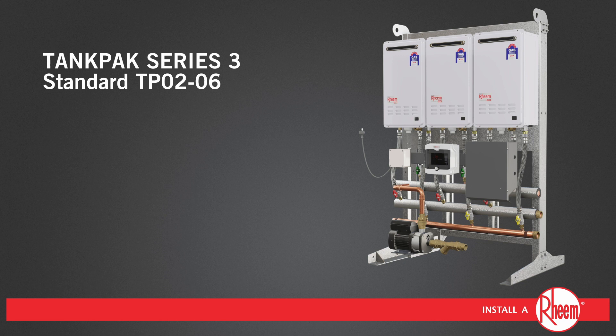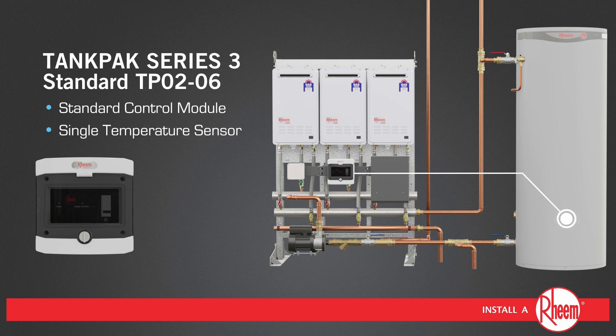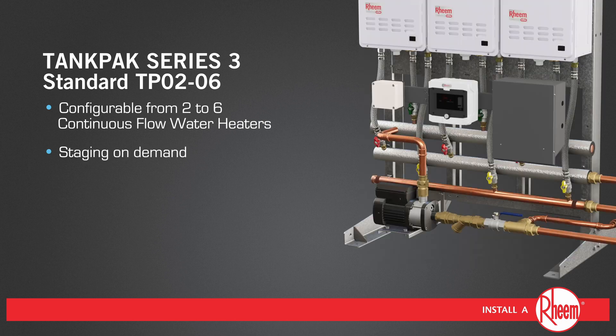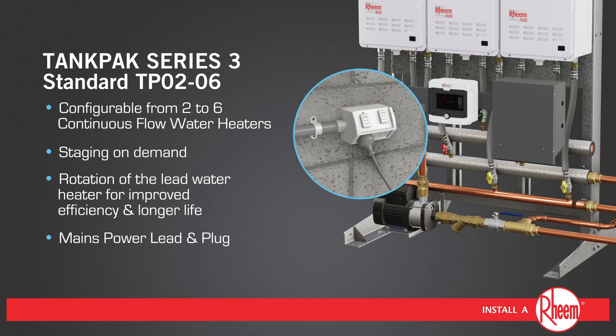TankPak Series 3 standard TP02 through to 06 is supplied with the standard control module and a single temperature sensor located at the bottom of the tank. The standard control module features trade adjustable temperature and pump control. TankPak standard features a single primary pump and can be configured from two to six water heaters with staging on demand and rotation of the lead water heater for improved efficiency and longer life, and is supplied with a mains power lead and plug.